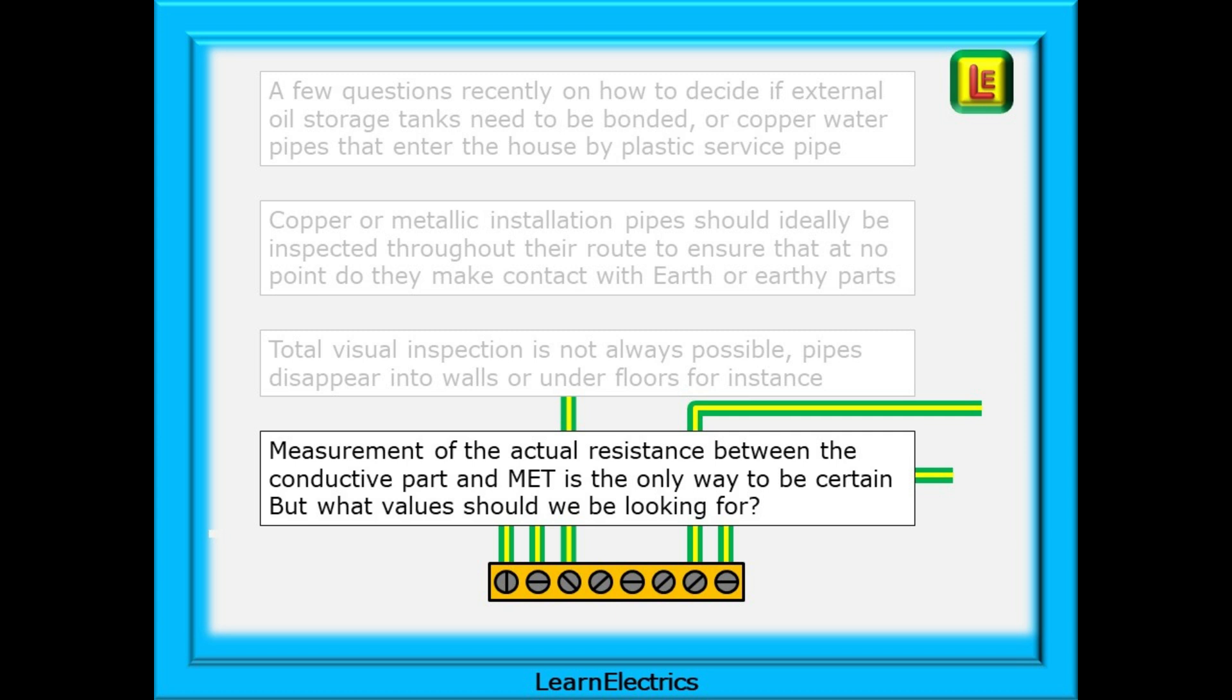Which means that a measurement of the actual resistance between the conductive part and the main earth terminal is the only way to be certain if that conductive part or metal pipe should be bonded or not. But what values of resistance should we be looking for?